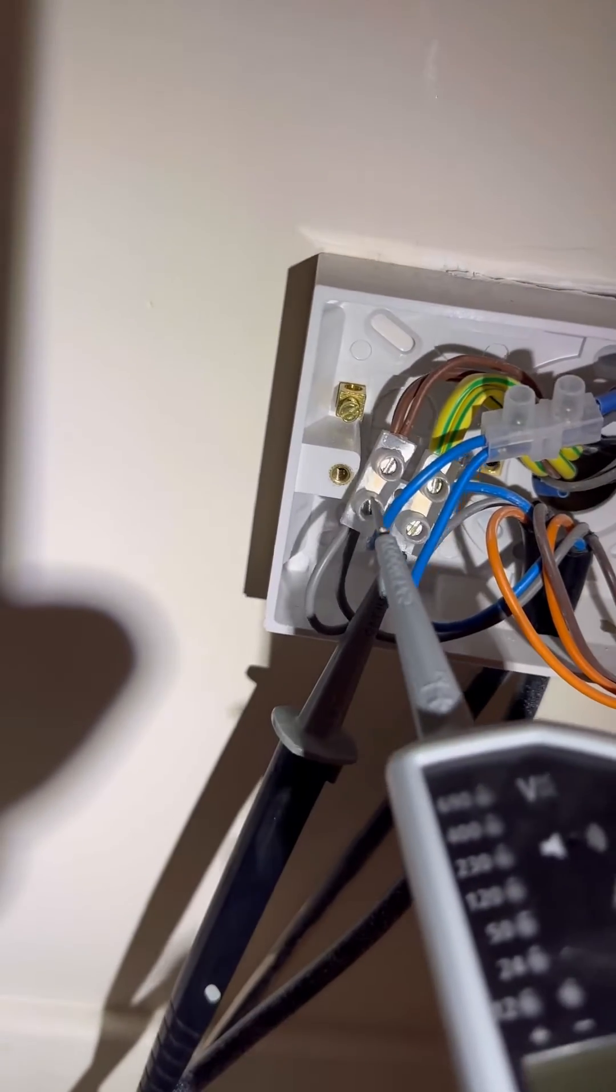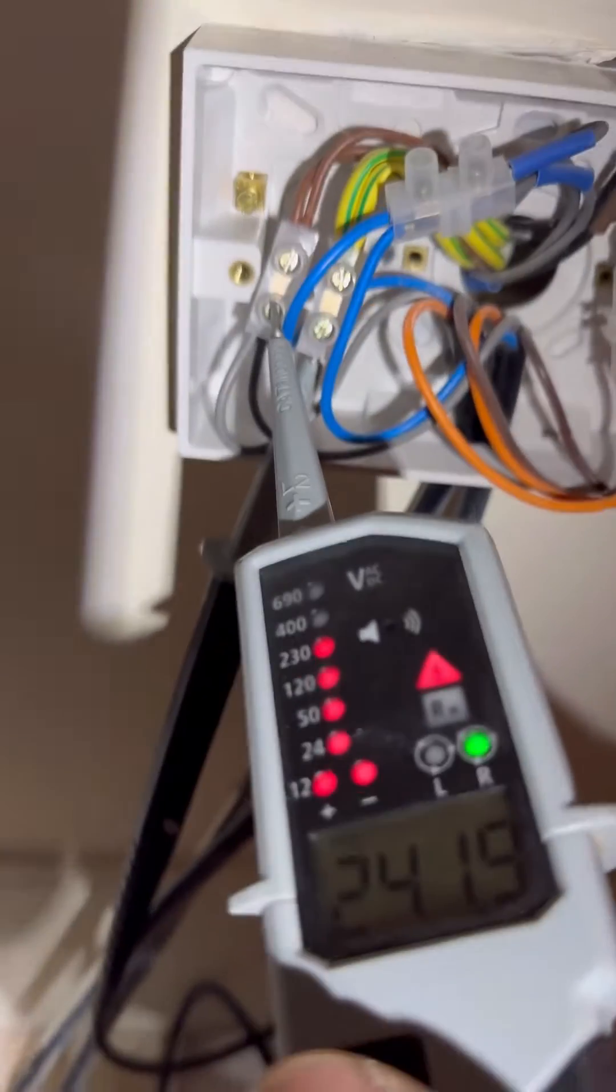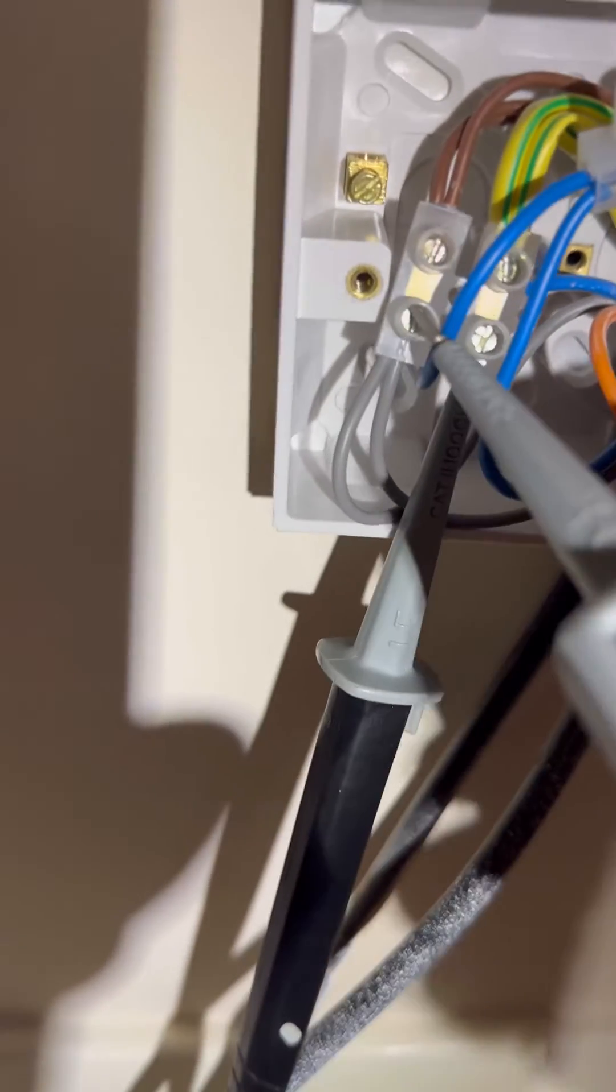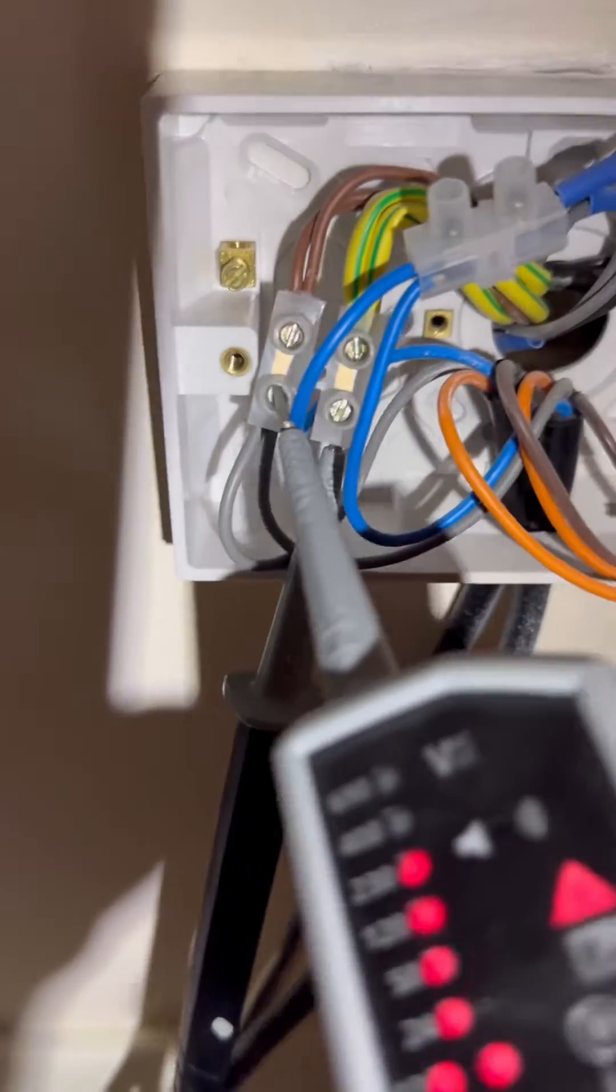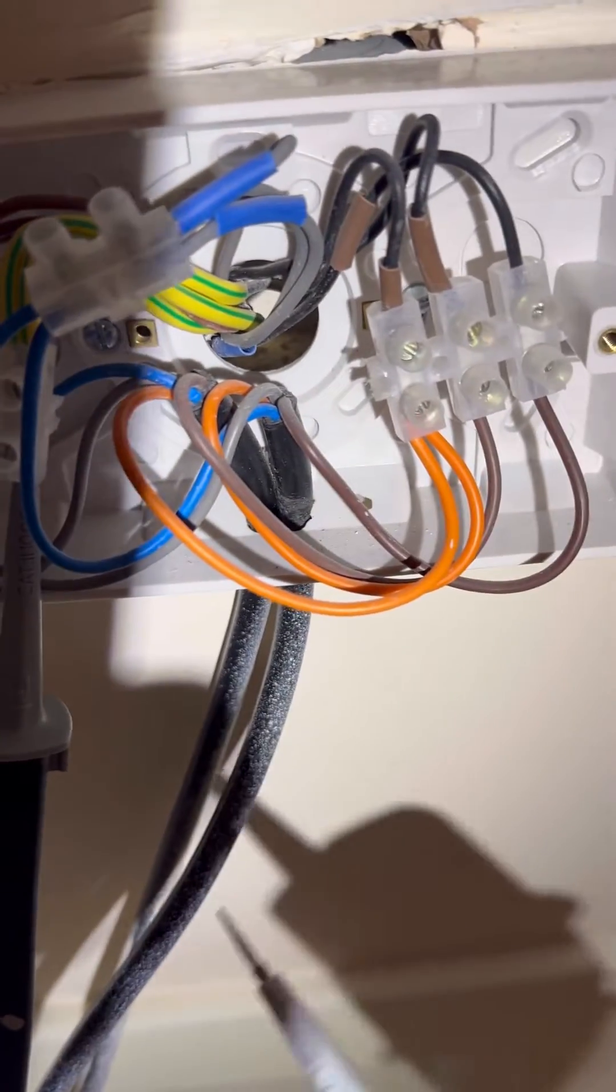So first thing I'm going to check is the gray. We've got permanent live to the zone valves, yeah. I'm getting 240.